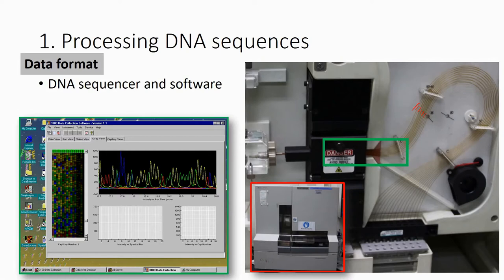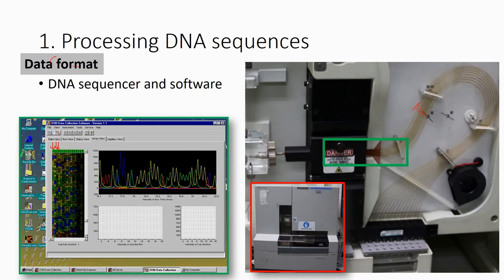You can see the first capillary, second capillary, and so on. You see the different colors. This is how it looks in the image. After that, the software interprets these colors and turns them into peaks. Different peak colors represent different nucleotide types.